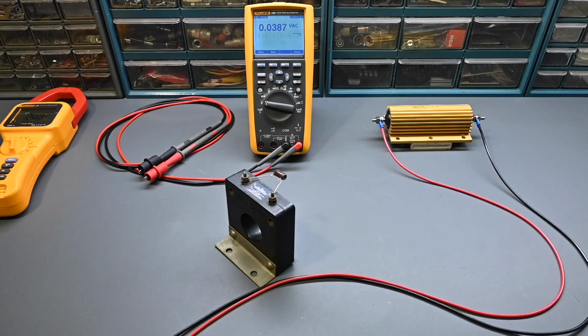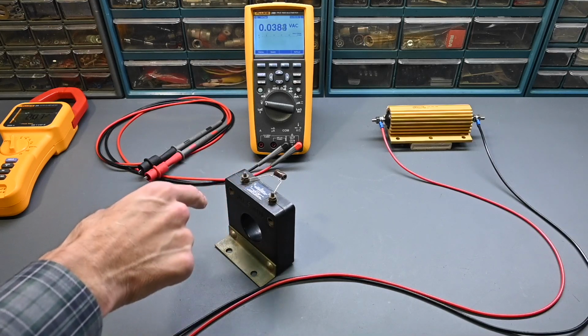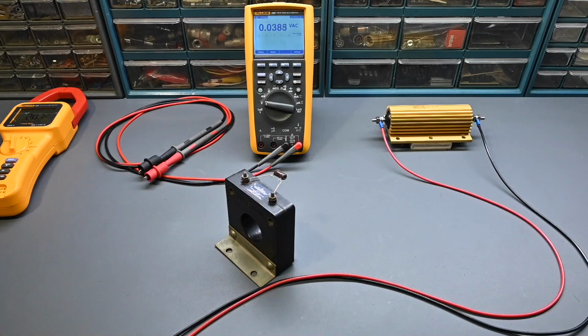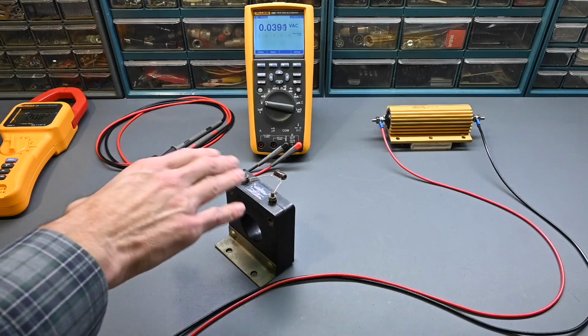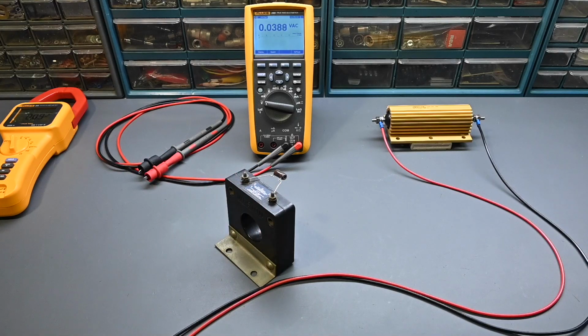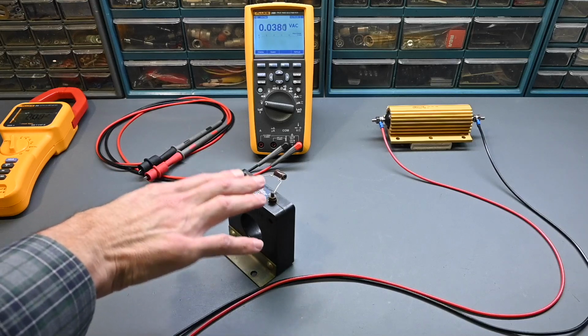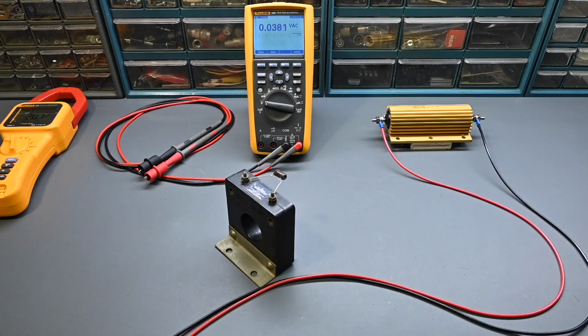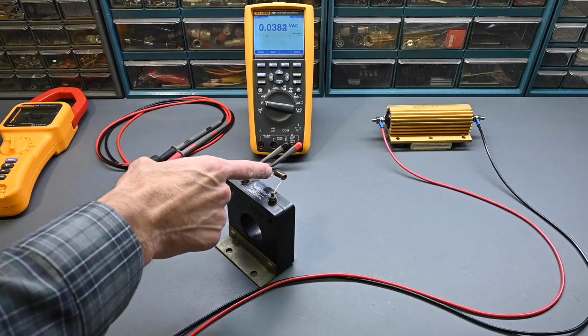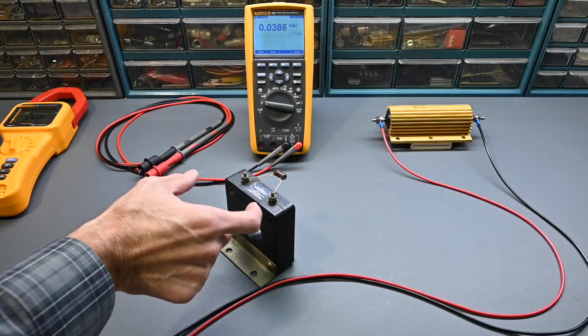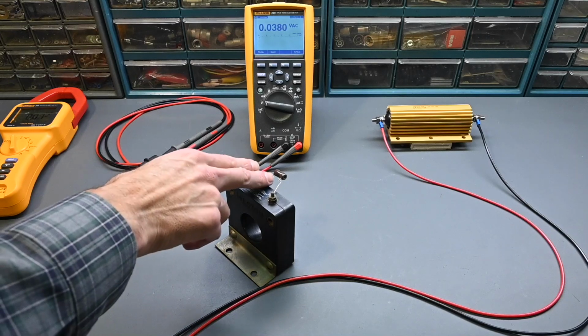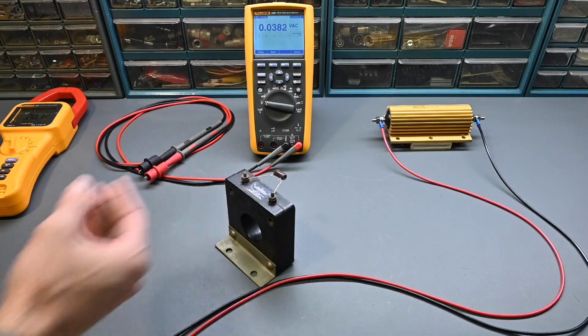Now you always need to operate a current transformer with the secondary terminated by a load resistor. Otherwise the transformer can be damaged by high voltage that builds up on the secondary, because it's acting like a step-up transformer. So you can see I have this resistor right here. It's 150 ohms. I have it across the secondary. It's just a random value that I've picked. It should be perfectly fine for this test setup. And this resistor will affect the readings or the calibration that you're getting off of the transformer. So this won't be calibrated. The actual voltage that this develops isn't something that you can just read directly and convert to current, because I have no idea what effect this resistor will have as far as loading down this transformer. So it's very important that this resistor be chosen correctly, and possibly even be an adjustable resistor in the final setup.